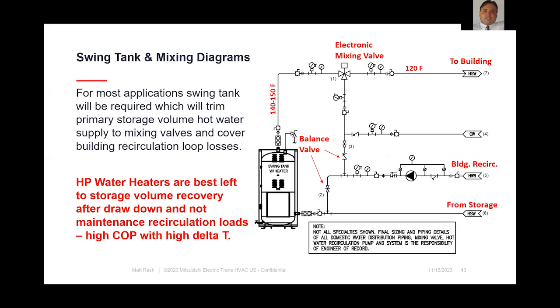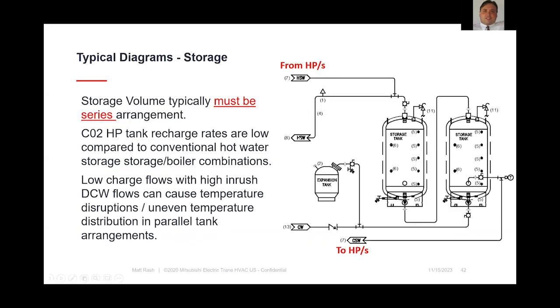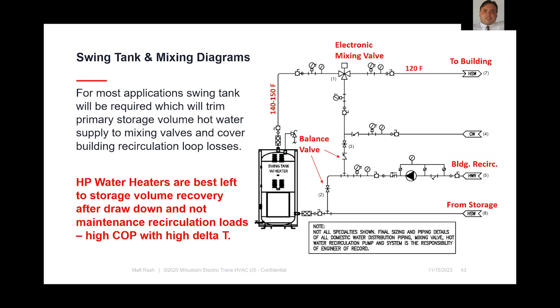And then again, on the mixing tank side, let me back up here. The hot water supply from this hot tank, again, you've got hot water coming from the heat pumps, but you've also got hot water leaving this tank, going not directly to the mixing valve, your main mixing valve for your building domestic hot water, but first going again from the storage to that swing tank. So again, the swing tank's going to handle that steady state idle load, that maintenance load for that building heating hot water recirc loop. So you're going to have that pump that would be by others. And again, this is pretty common and typical on this side, the recirc side with mixing valve for most domestic hot water systems. So you'll have your recirc water coming back from that pump. You'll have balance valves to redirect a portion of that through the swing tank, and then a portion back with cold city water into your electronic mixing valve typically.